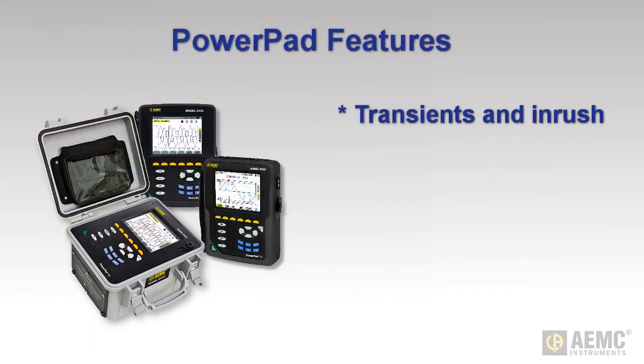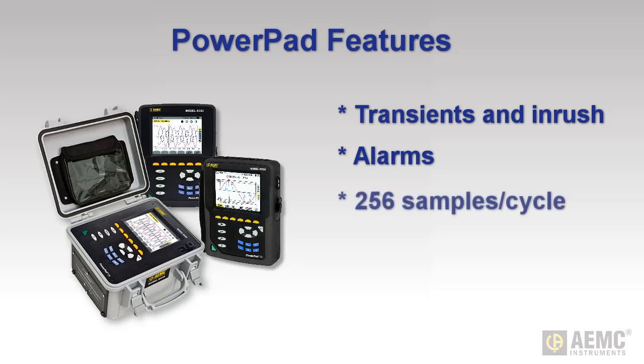The PowerPad can detect and record short-term anomalies such as transients and inrush current. You can also configure alarms to identify when a measurement falls outside defined parameters. The PowerPad takes 256 samples per cycle, resulting in over 15,000 samples per second on 60 Hz networks. These samples are used to calculate highly detailed sub-cycle data.